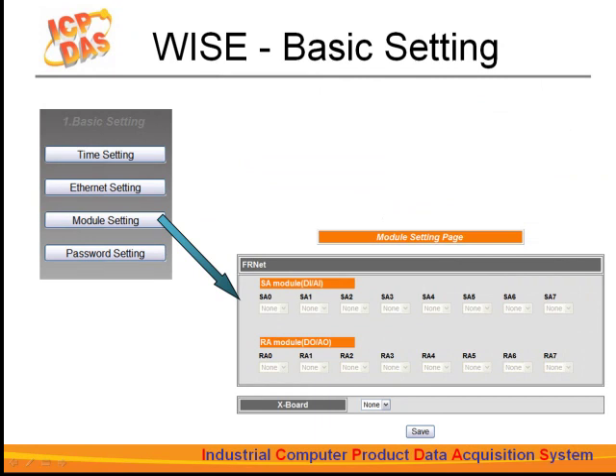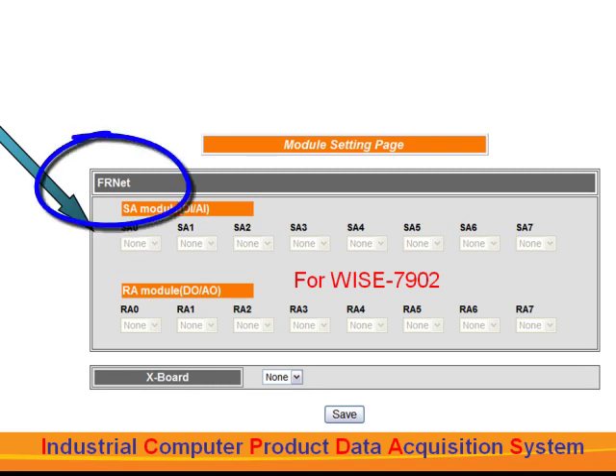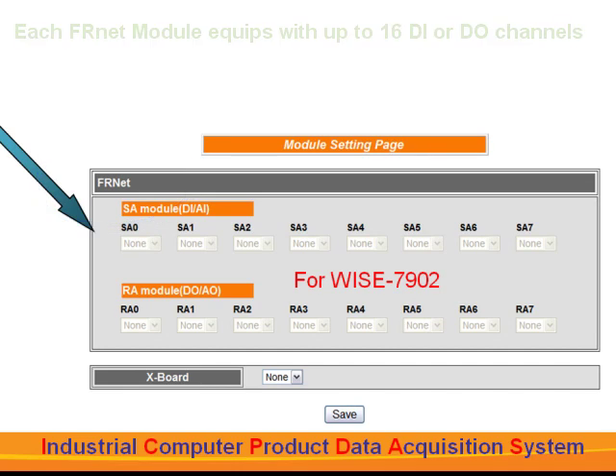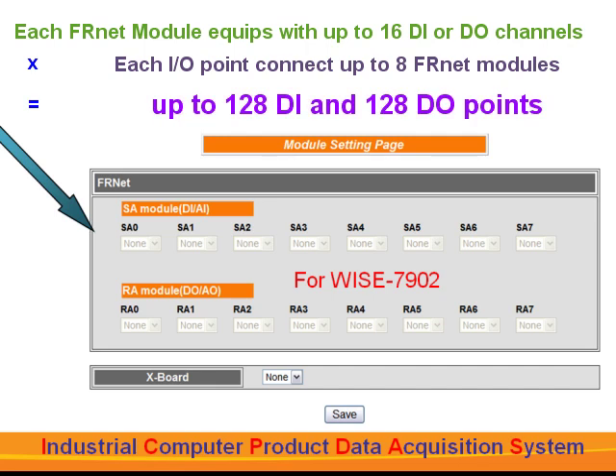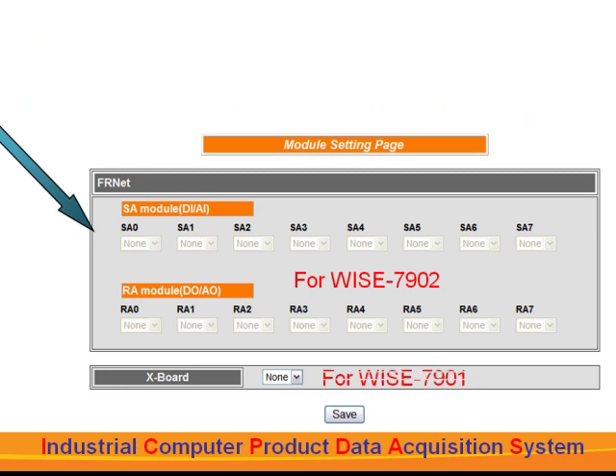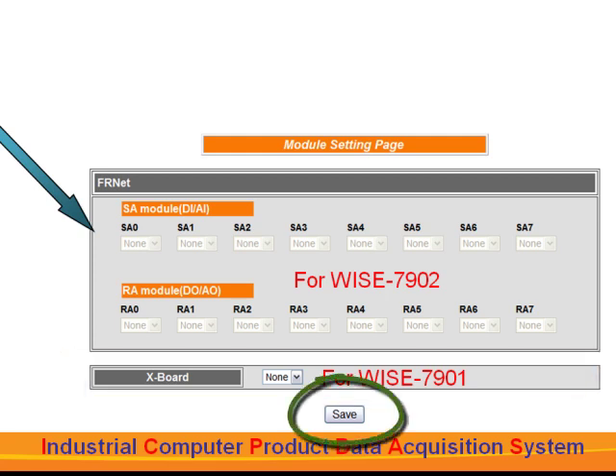The WISE 7902 module will be available soon. WISE 7902 is designed for connecting with ICP-DAS FR-NET modules, and is good for applications that require large-scale deployment. Each FR-NET module is equipped with up to 16 digital input or digital output channels. Each I/O point may connect up to 8 FR-NET modules, giving you up to 128 digital input and 128 digital output points. For each controller to function accurately, you will need to select the corresponding plug-in module type from the drop-down list and save the settings on this web page.